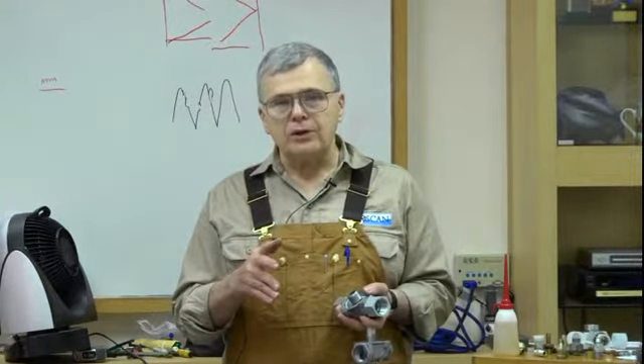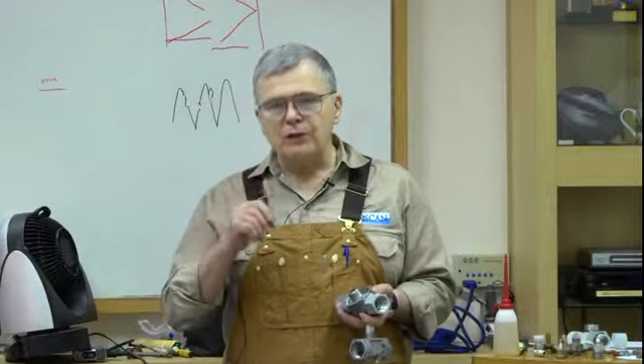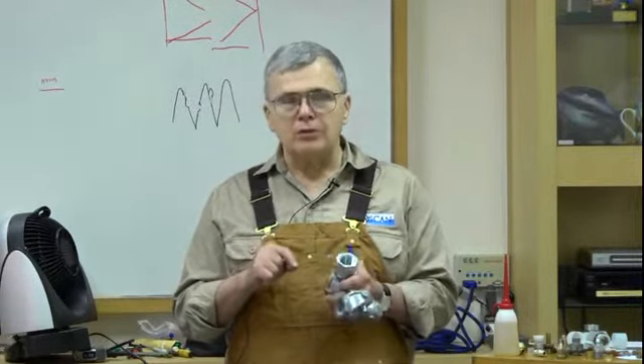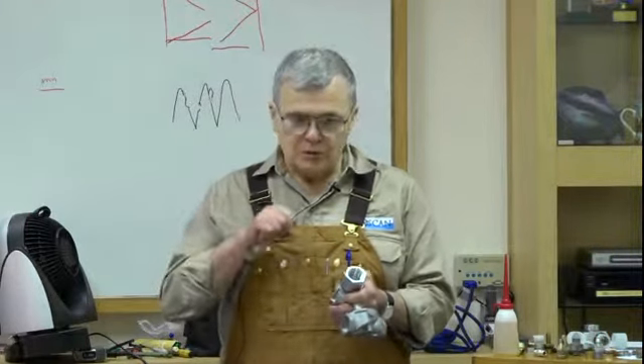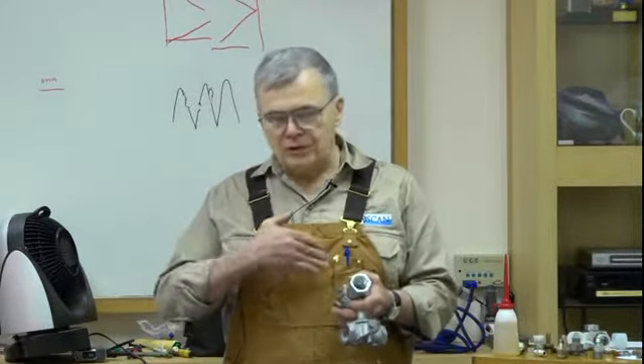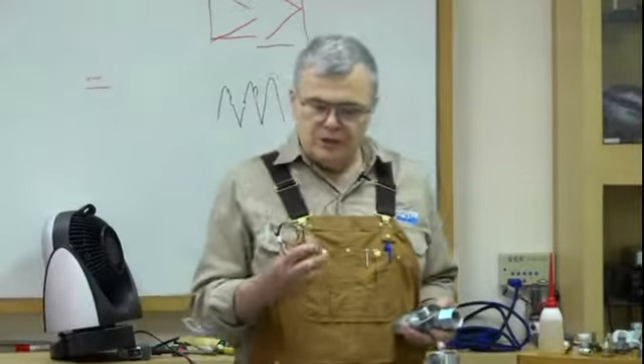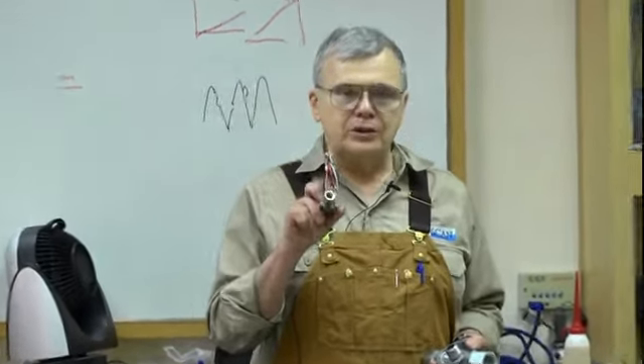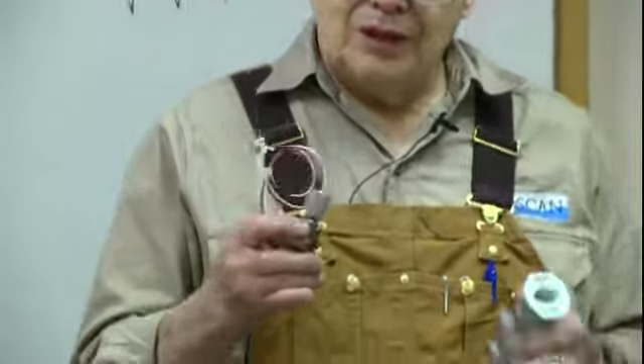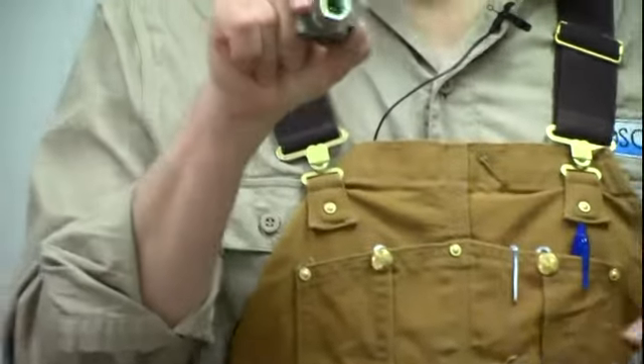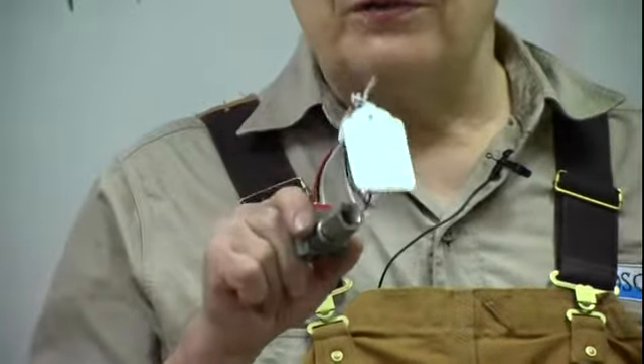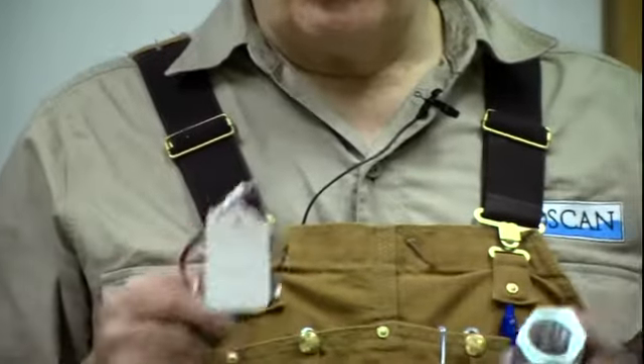That's important for our equipment because we want the fuel to impact the rotor consistently. If you had a lot of turbulence in the fuel, sometimes it would impact it harder, sometimes easier. You would get fluctuations. On our standard flow sensors, we don't have a flow homogenizer, but we have a flow straightener in there. That's a tube section. It has like 3 little openings in it, and it is very efficient, very effective at the lower flow rates that the standard flow sensor sees.